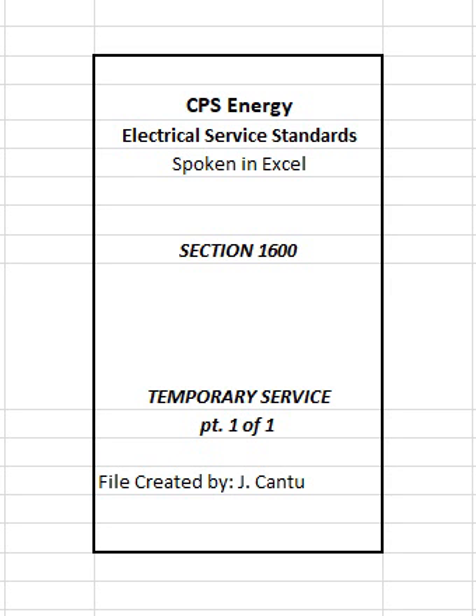1. Conduits shall be 1 1/4 inches minimum size unless otherwise specified by the CPS Energy Customer Service Representative. 2. Conduits shall be a type approved for direct burial and be rigid metal conduit, RMC, intermediate metal conduit, IMC, Schedule 40 or 80 PVC conduit, or flexible nonmetallic liquid tight conduit. Where flexible nonmetallic conduit is used, it shall be left long enough to extend into transformer or secondary enclosure. 3. Conduits shall be buried with not less than 12 inches of cover to the top of conduits from final grade and be provided with marker warning tape to warn excavators and to prevent damage or personal injury.